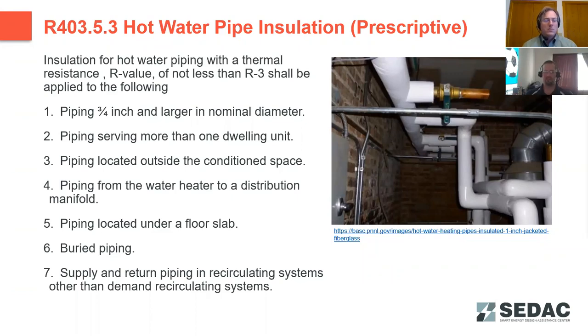Piping located under a floor slab. Again, you're trying to isolate any heat losses to the cooler ground temperature. Any buried piping, again, that ground temperature disconnect. And supply and return piping in recirculating systems other than demand recirculating systems. Recirculating systems being ones that recirculate water continuously. Demand ones have that exception because they're not circulating that water continuously and thus have fewer losses overall.